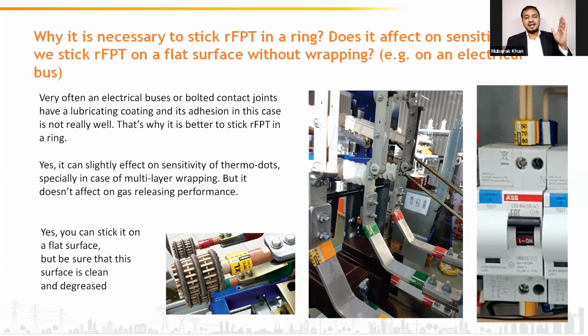So in the bus bars, the stickers will be installed like this in the circuit breaker panels, in the bus bars, etc. Okay, and in the circuit breaker jaw connections, the stickers will look like this. Normally, it is recommended to wrap the stickers around the joint just to make sure that the sticker doesn't fall down because of the loss of adhesiveness. Otherwise, it will effectively work when installed in any way possible. But normally it is recommended to wrap it around the joints. Around the joints means near the joints.